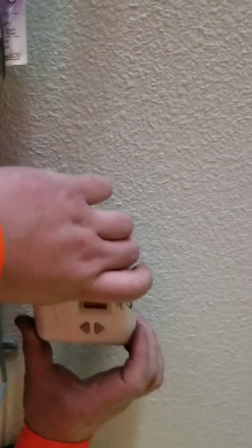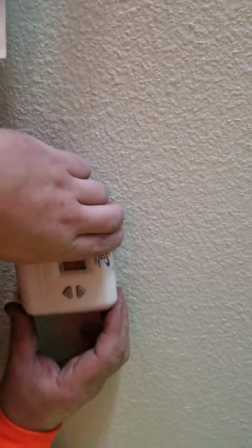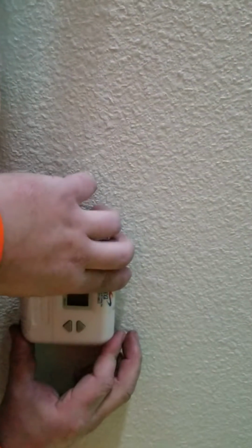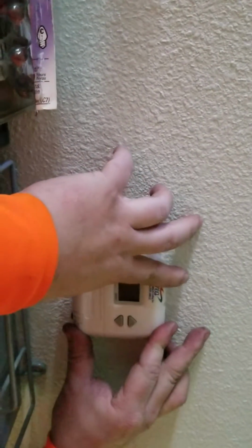I'll slip that back off. See this here. Let's lay these down a little further so that they don't get pinched on the edge. There. That means the insulation on that wire is very thin. It does not take much to go through that insulation and cause a problem.